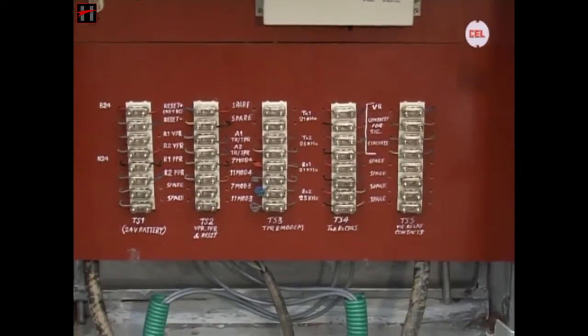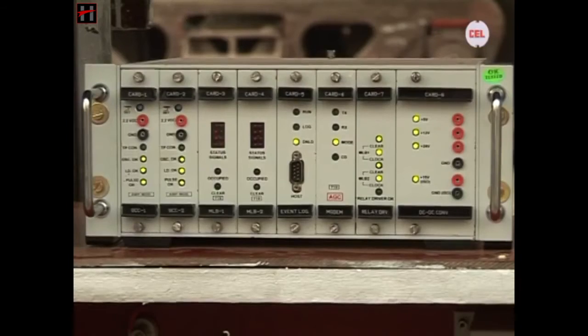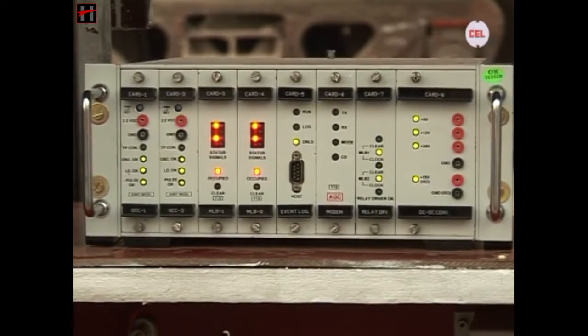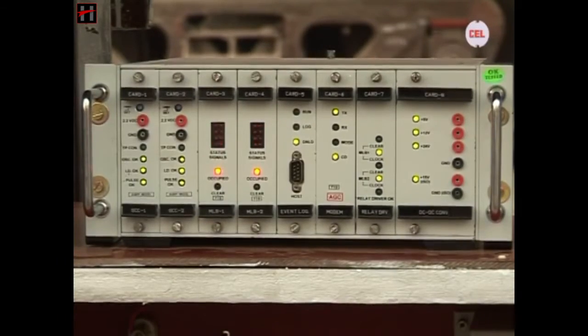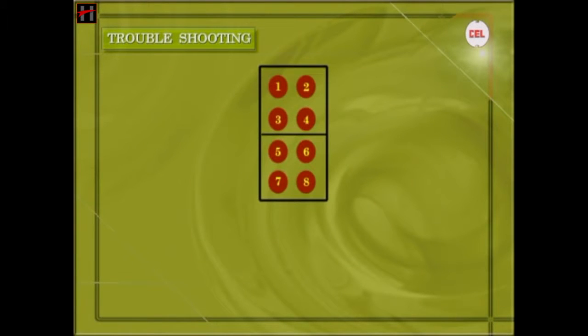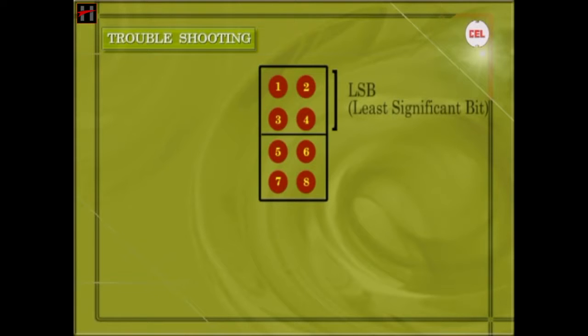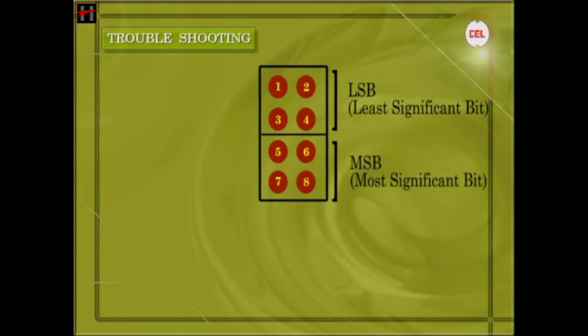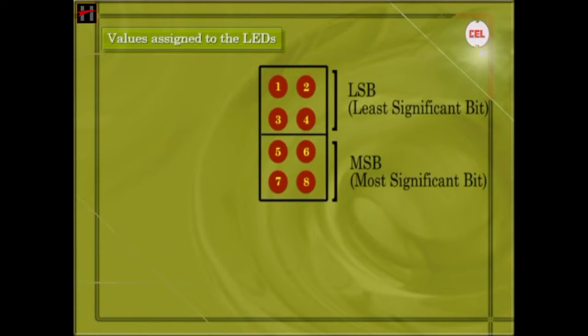The errors occurring in the system during the operation of SSD AC are encoded and indicated by means of the 8 LED block present on the front panel of the MLB cards. All the LEDs are numbered as given: DS1 to DS4 are designated as the least significant bits or the LSBs, and DS5 to DS8 are designated as the most significant bits or the MSBs. Each of these LEDs has a corresponding value assigned to it.